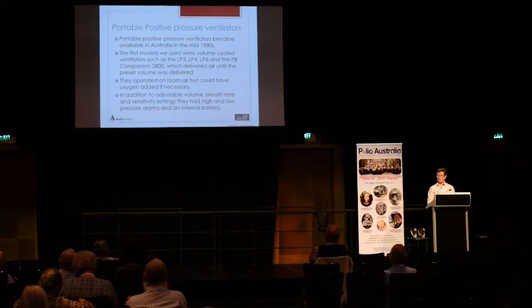And in addition to delivering an adjustable volume, breath rate and sensitivity, they also had high and low pressure alarms and an internal battery, so that if there was an issue with the individual, say someone was being ventilated by tracheostomy and they became disconnected, the alarm would go off so that the staff member would be alerted to an important problem and would attend quickly. And also the internal battery gave you a couple of hours of operating time in the event of a power failure.